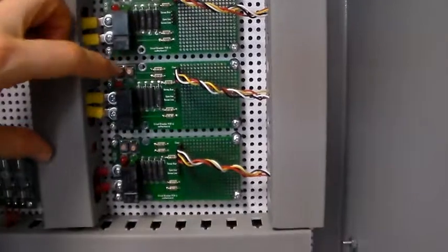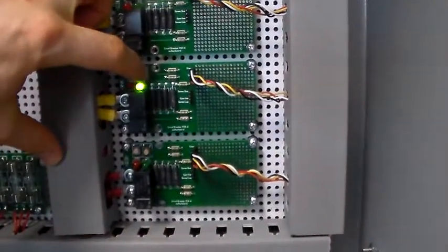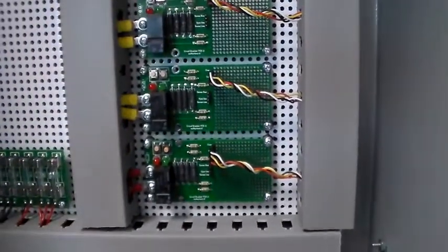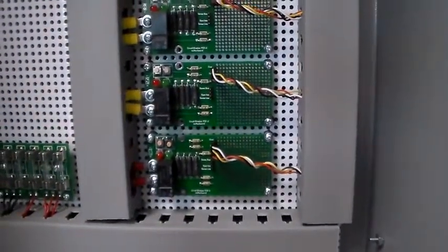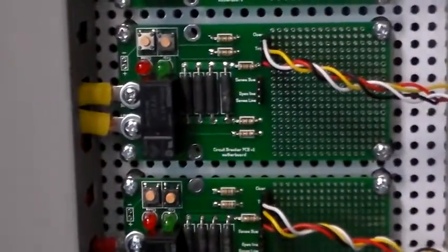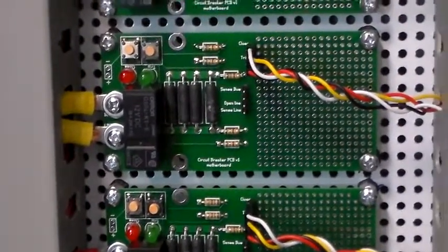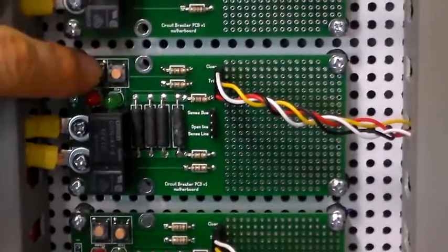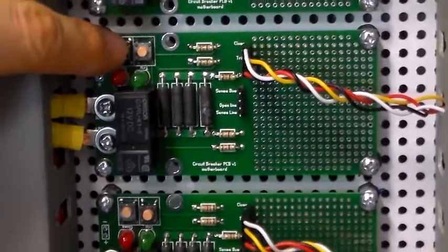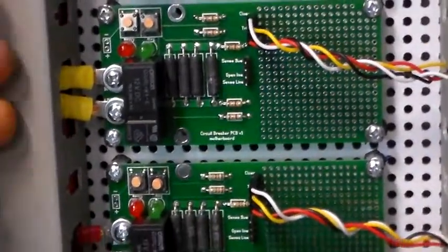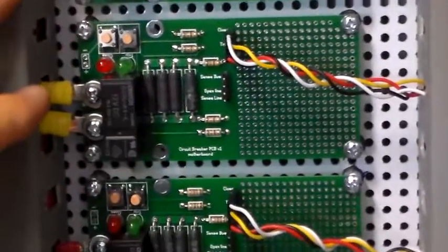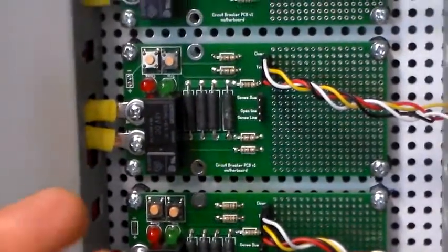Now to trip the breaker, to turn it off, you press the button next to the green light. That turns the power off to the West cabinet. Now at first the color scheme may seem backwards, but in the electric power industry this is actually the way it's done. Instead of green meaning go and red meaning stop, green is off or safe, and red is on or energized or dangerous. Even though there's no actual danger here, this is all very low voltage, you can't possibly get shocked here. I'm going to push the button with the red. That will close the breaker, sending power to West cabinet.